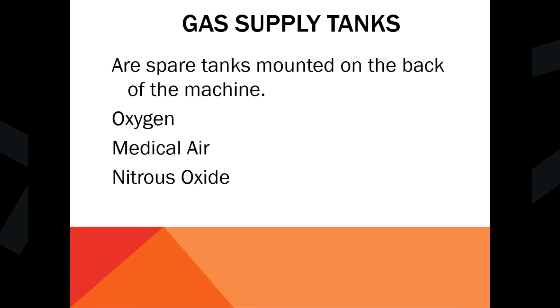Another thing that's optional but probably recommended is that you have backup tanks. In the unlikely event that you lose your house gas, you can turn on the gas on the back of the machine and continue on with your case. These include oxygen, medical air, and nitrous oxide. Down here you'll have a little manifold. This would be your oxygen, then you would have a medical air tank back here, and then you could put an auxiliary tank, which would more likely be your nitrous oxide. And then over here you have your house gas. They come off of a manifold on the back of the machine, and you can see the hoses going either to a boom or to the wall.